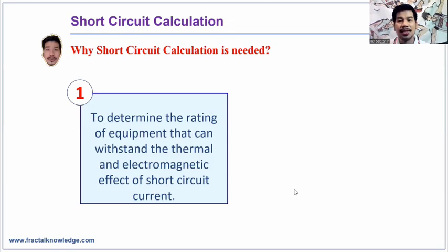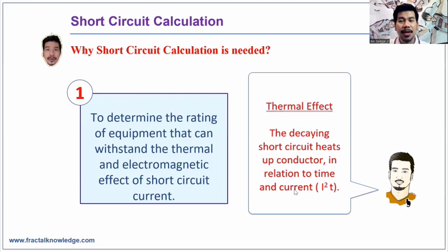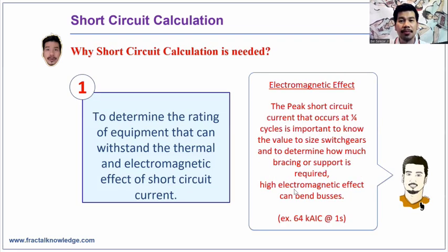The first reason is to determine the ratings of equipment that can withstand the thermal and electromagnetic effect of short circuit current. The thermal effects of short circuit current heats up the conductor in relation to time and the square of the current. The electromagnetic effect that occurs on the one-fourth cycle of the sinusoidal wave when the fault occurs is the power of the fault which can bend buses and damage switchgears, even take away life.